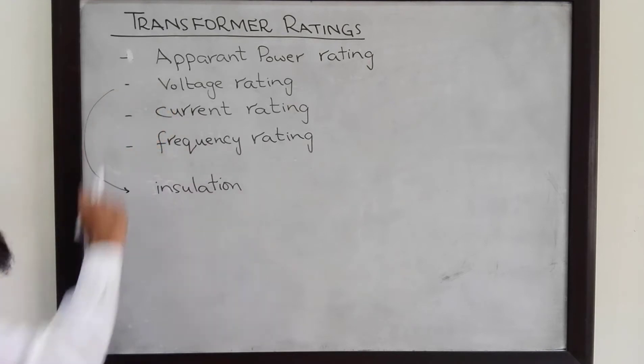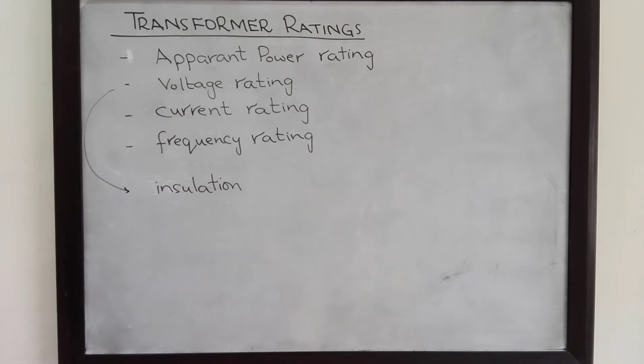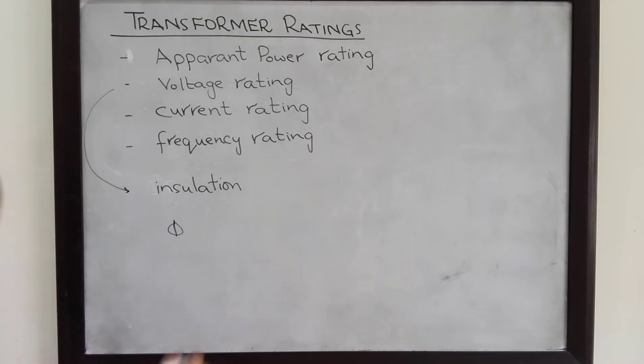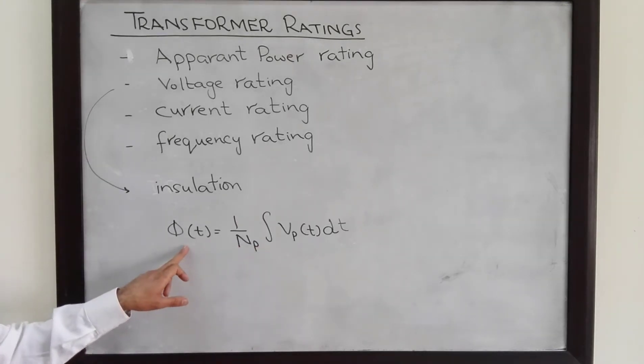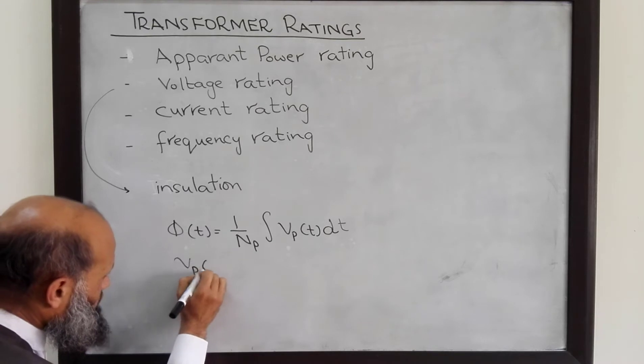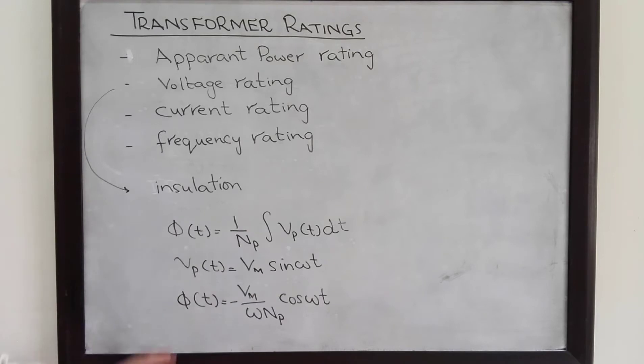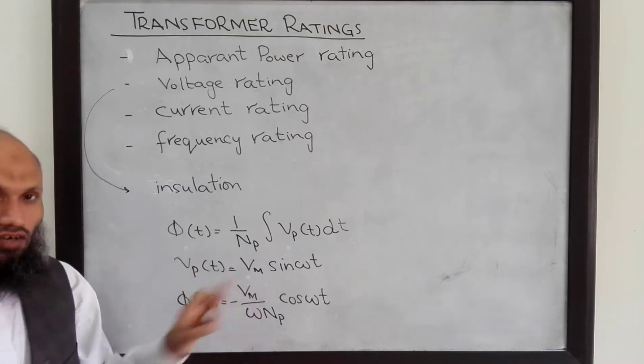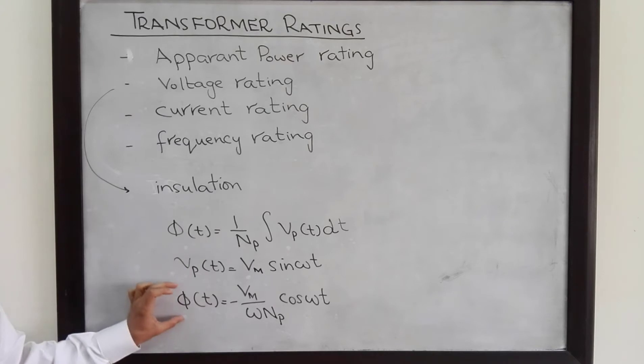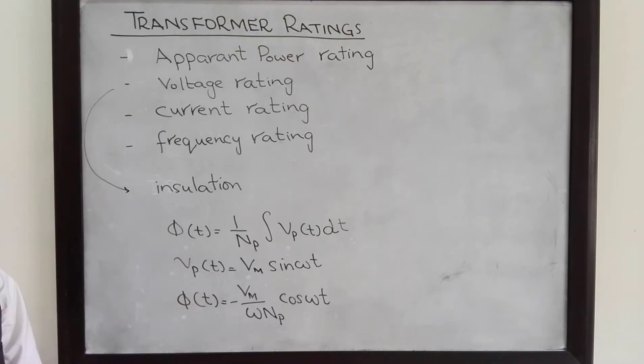There is another aspect which limits the maximum voltage that can be applied to the transformer. To understand it, let's see the relationship between the flux and the voltage. We know that the flux in the transformer is related with the voltage by this expression: phi(t). This relation relates the flux flowing in the transformer and the primary voltage applied. If we apply this primary voltage vp(t), then the flux will be given by this relation — that is, the maximum value of the flux depends upon the maximum value of the applied voltage. And if there is an increase in the maximum value of the applied voltage, there will be an increase in the maximum flux flowing through the transformer.